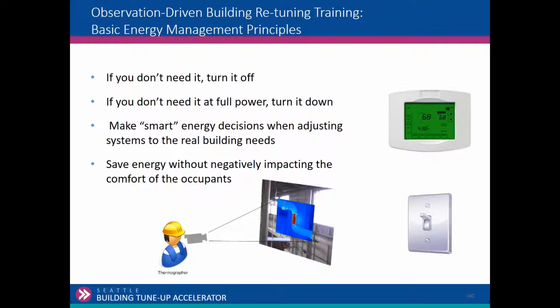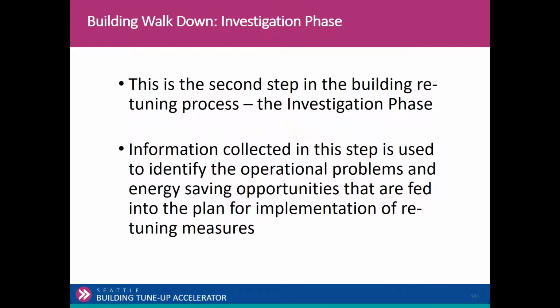Saving energy without negatively impacting the comfort of the occupants. We can all save a bunch of energy. We'll just set the thermostats at 68 for heating. Right? So we want to keep in mind, it said looking at set points, but are they reasonable? One thing I've learned about comfort is that if you don't provide it, people will take control of it. They'll bring in the space heaters, right? So that's an issue of comfort issues: space heaters, fans, sabotage. Those are all symptoms of comfort. So those are some of the themes that we want to keep in mind as we're going through this.